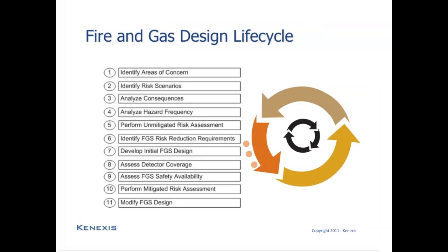Now, the ISA 84 Technical Report 84.00.07 has defined a life cycle for the application of fire and gas systems. This life cycle is very similar in nature to the safety instrumented systems life cycle in the IEC 61511/ISA 84 standard, but adds a few more issues that are directly related to the fire and gas systems. So the life cycle that's defined in ISA TR84.00.07 starts with identifying areas of concern.